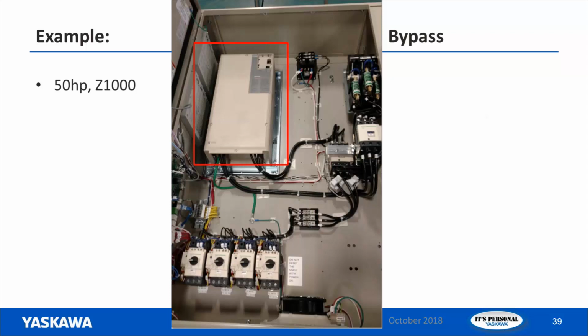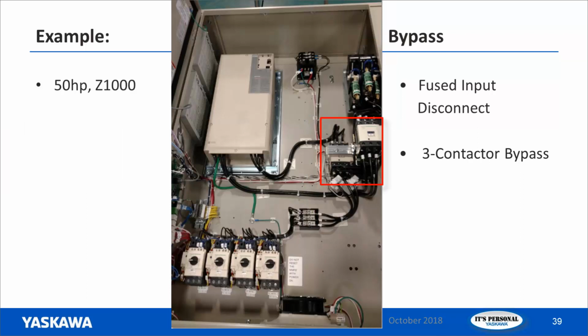Right here we have a Z1000 drive. It's a 50 horse. Right here we have our fused disconnect input. In this particular example, this is a 3-contactor bypass, so we've got our 3 contactors here. And right here we have our 4-motor array. These were four 10-horsepower motors, and notice we are using MMPs in this configuration. It makes it pretty neat and tidy.